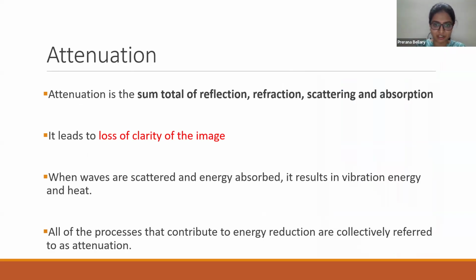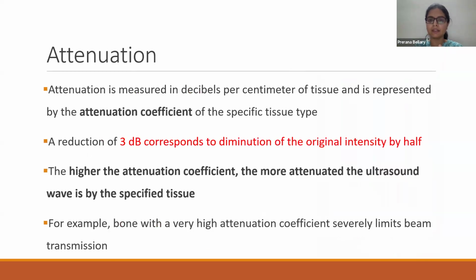Attenuation is the sum total of reflection, refraction, scattering, and absorption. And what it does is it leads to a loss of clarity of the image. So when waves get scattered and energy gets absorbed, it results in vibration and heat. And all of the processes that contribute to energy reduction from the probe are collectively referred to as attenuation. This is measured in decibels per centimeter of tissue, and it gets denoted by attenuation coefficient. So a reduction of 3 decibels corresponds to a decrease of the original intensity of the ultrasound wave by half. So higher the attenuation coefficient, more will be the attenuation of the ultrasound wave by the specified tissue.